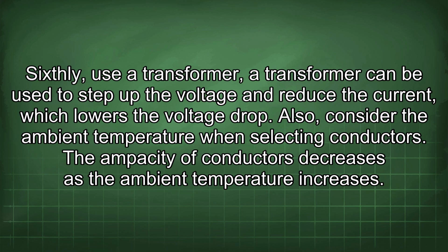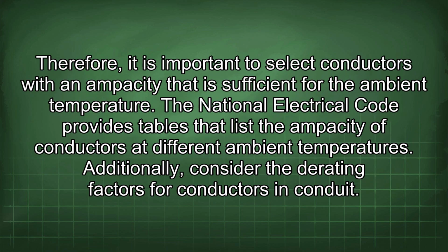Also, consider the ambient temperature when selecting conductors. The ampacity of conductors decreases as the ambient temperature increases. Therefore, it is important to select conductors with an ampacity that is sufficient for the ambient temperature. The National Electrical Code provides tables that list the ampacity of conductors at different ambient temperatures.